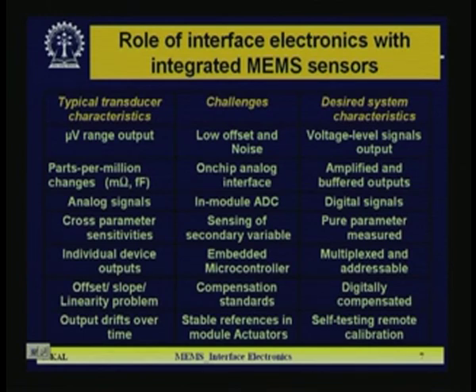Next is offset, slope and linearity problem. These are the inbuilt problems of any kind of sensor. Offset will be there, and linearity is desirable but all sensors will have some non-linearity. So to get rid of that problem, compensation standards should be there, and people prefer compensation digitally.